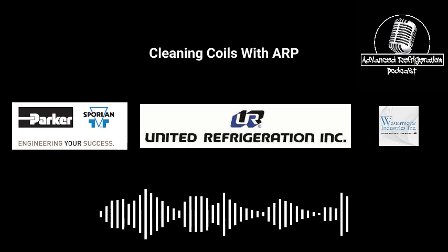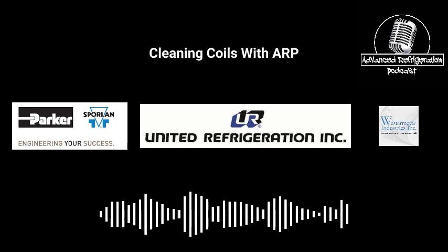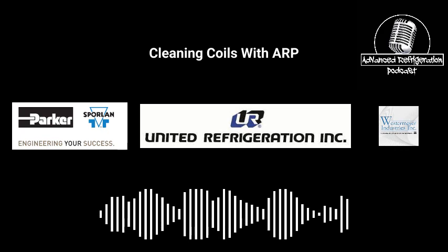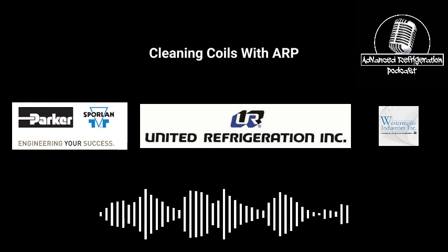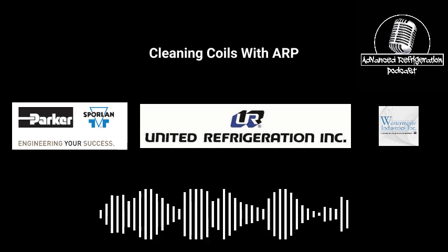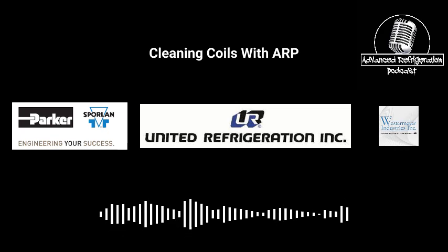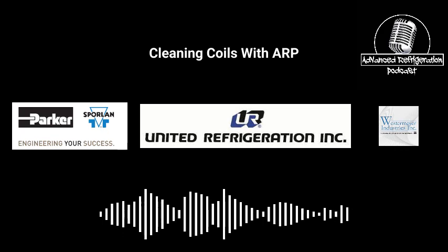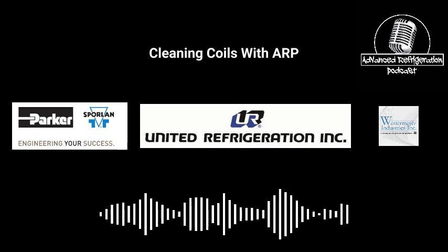The Hotsy has a kerosene heater on it, and it's heating up the water to almost boiling. So it'll just remove grease off stuff. If you're doing that and you power wash the rack too, it'll literally just melt the grease right off the rack. It does the same thing for grease on condenser coils. It'll melt the grease out without having to use chemicals. Like if you're at Costco, the Hotsy is awesome, because you can't use chemicals on the roof. So that Hotsy to clean the condenser works great.